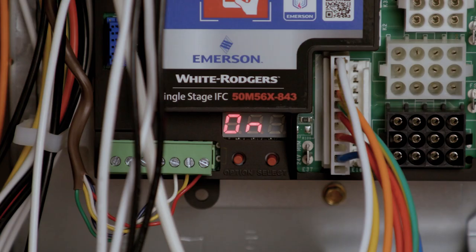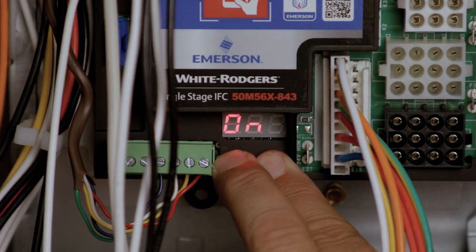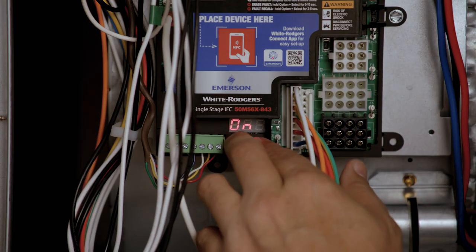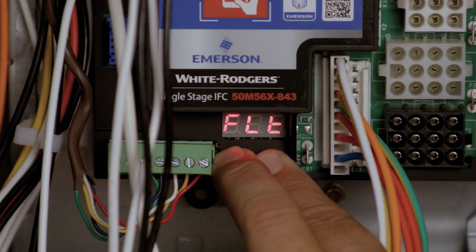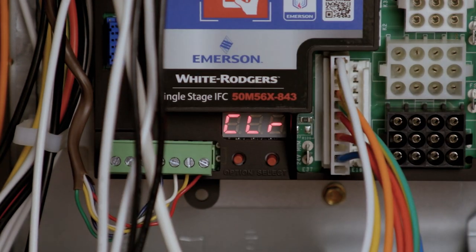Fault codes can also be accessed on the module anytime the module is powered. Press the Option and Select buttons for 2 to 5 seconds. If there are no errors, the display will read On. To clear errors using the module, hold the Option and Select buttons together for 5 to 10 seconds. This action can be performed whenever the control is powered on.